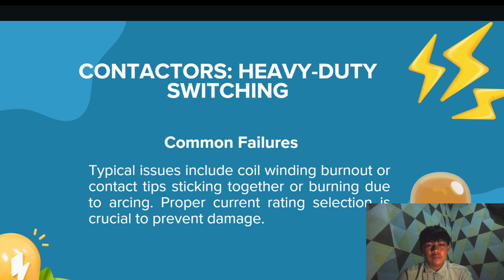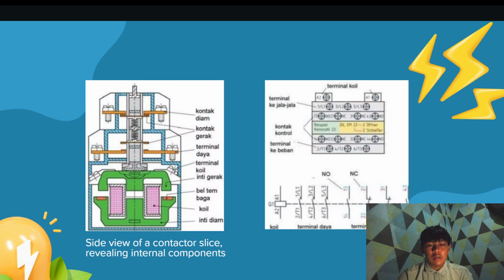Common failures. Typical issues include coil winding burnout or contact tips sticking together or burning due to arcing. Proper current rating selection is crucial to prevent damage. And this is the raw side view of a contactor slice. This is the static contact, this is the dynamic contact, this and this are the terminals for the coil, and all that.